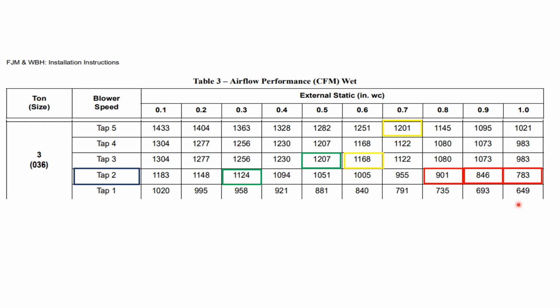So understanding that, now what do you do? Well, most people would say, I'll move it up to speed tap 3 because I see there's some 1200s up there. And that's correct. You could do that, providing your static pressure doesn't move. Now, how do you check this? Well, there's a podcast we've done that is solely on static pressure. So you would take your dual manometer, and I use a Fieldpiece dual manometer. I have the Bluetooth ones, and I also have the SDMN6 packet that has the duct probes. Put them in, and I'll read what that static pressure is.